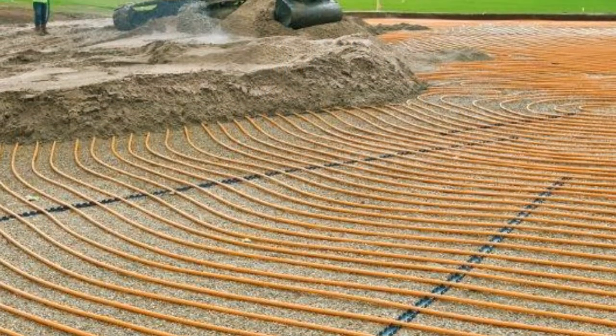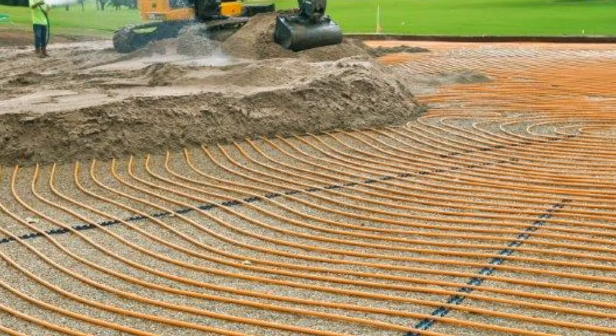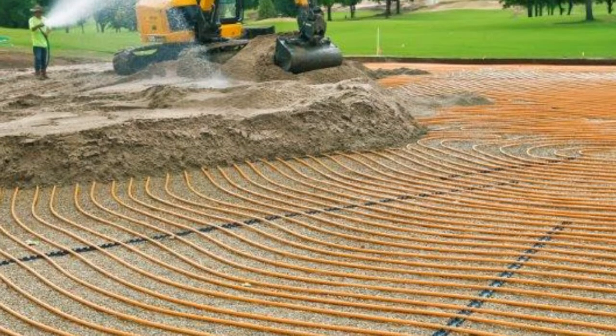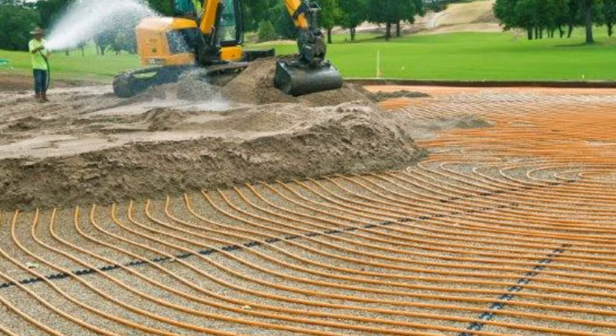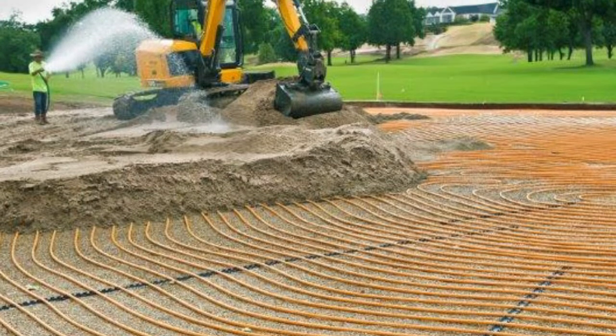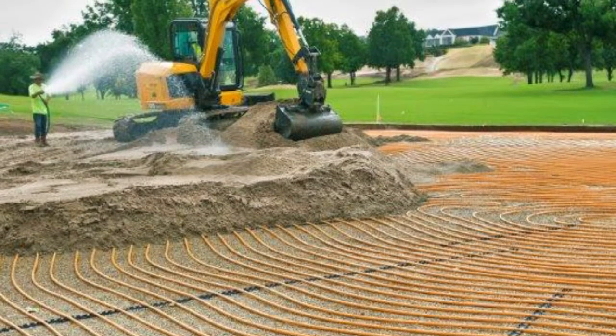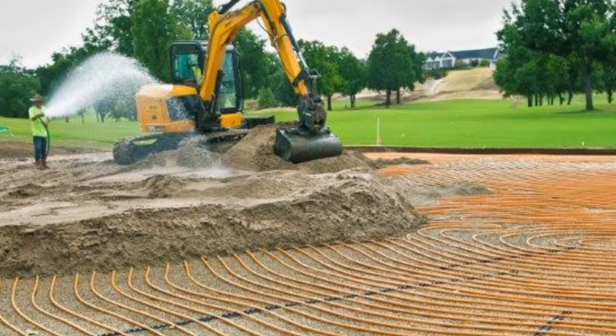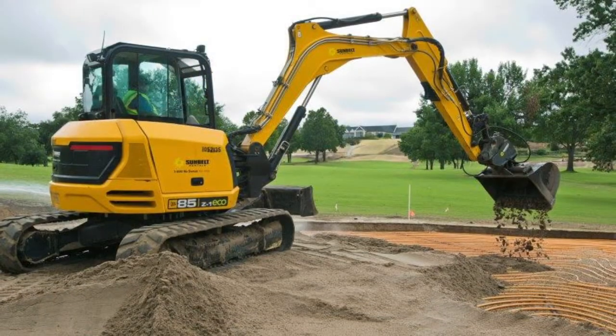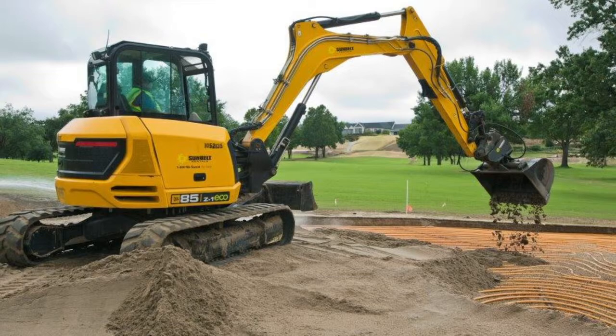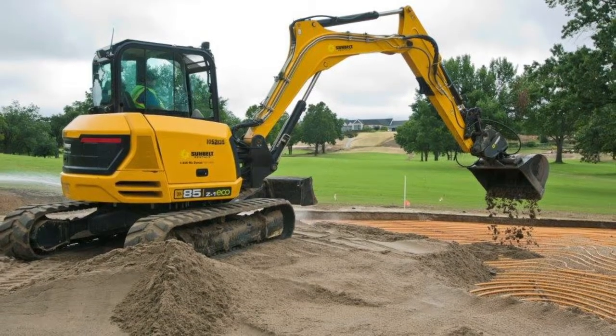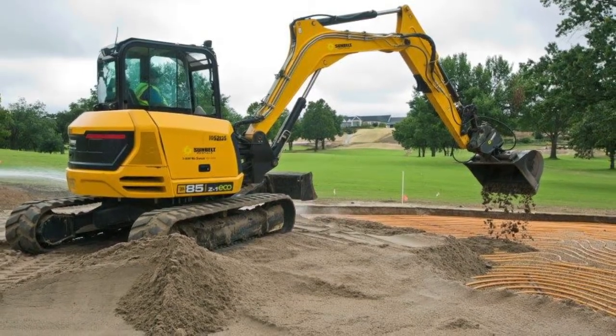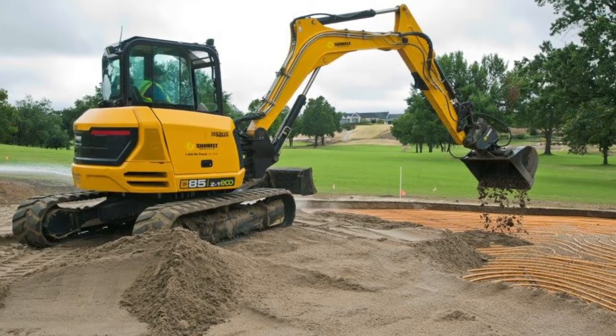The greens required 3.5 tons of cooling per 1,000 square feet. This would allow soil temperatures to be lowered by 15 degrees, maintaining between 65 and 80 degrees throughout the year. The proposal ended up with 4 heat pumps serving the entire course: a 200-ton, 133-ton, 123-ton, and 110-ton pump. The heat pumps were custom designed to meet Southern Hills requirements.